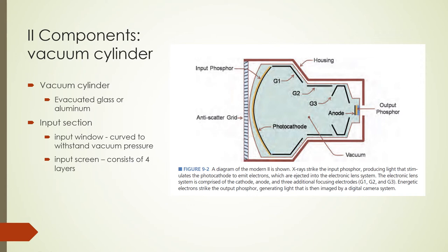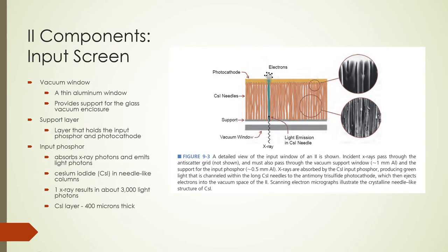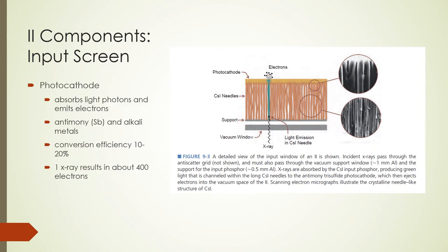The first layer in an image intensifier is a vacuum window — a thin aluminum window that protects the glass vacuum enclosure. The second layer is a support layer consisting of the input phosphor and photocathode. The input phosphor, the third layer, converts x-ray photons into light photons and plays the role of the screen as in general radiographic imaging. It is typically made of cesium iodide crystals grown in needle-like columns, about 400 microns thick. Because of its sensitivity to x-rays, one x-ray photon results in about 3,000 light photons being produced. The photocathode, the fourth layer, converts light photons from the cesium iodide into electrons by means of the photoelectric effect. It is made of antimony and alkali metals with a conversion efficiency of 10 to 20 percent, releasing about 400 electrons per absorbed x-ray photon.